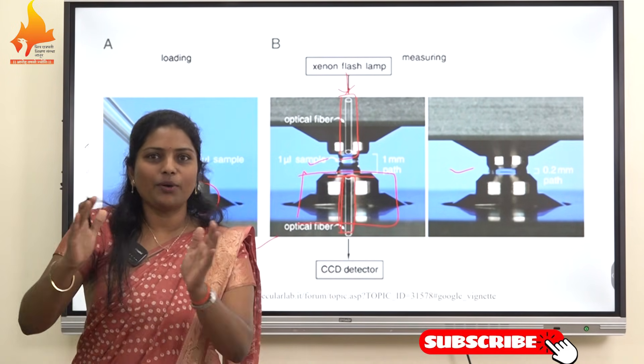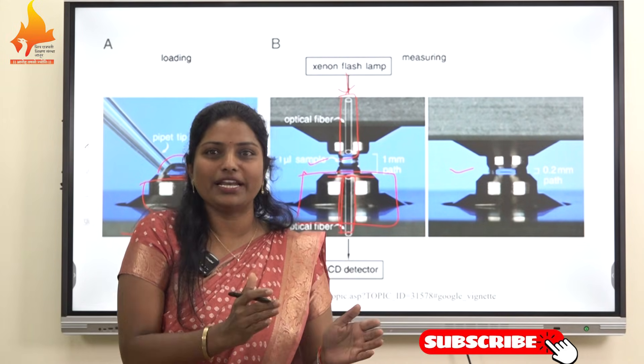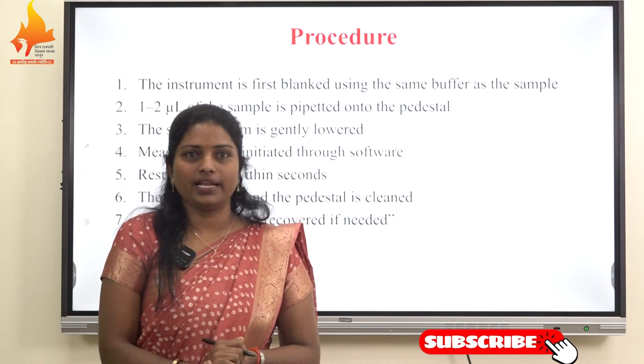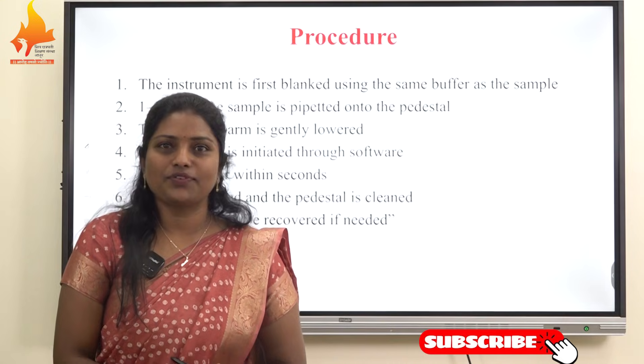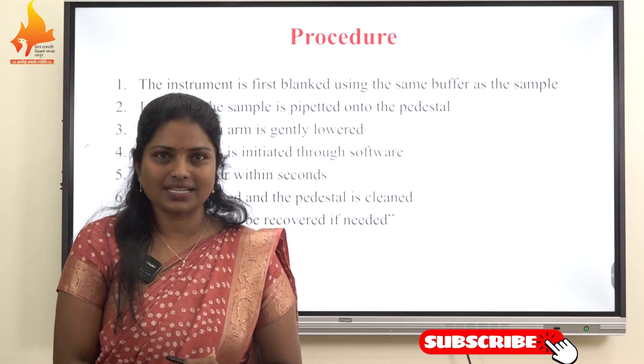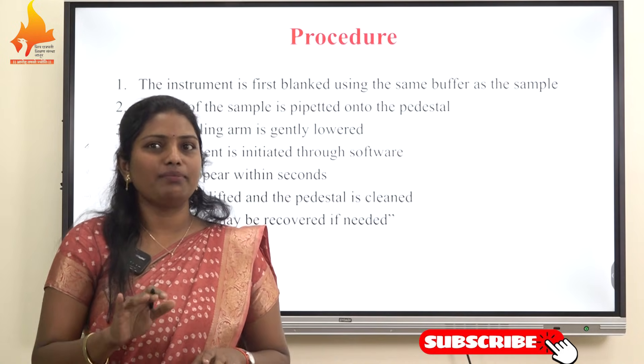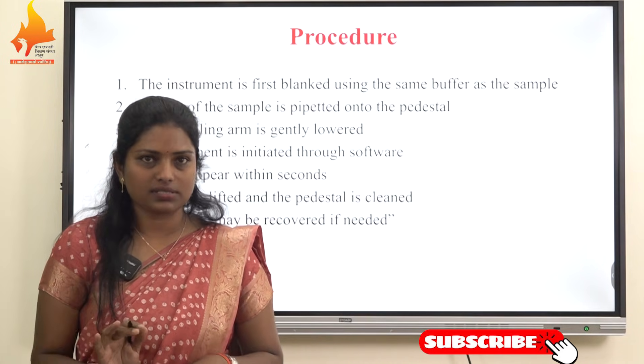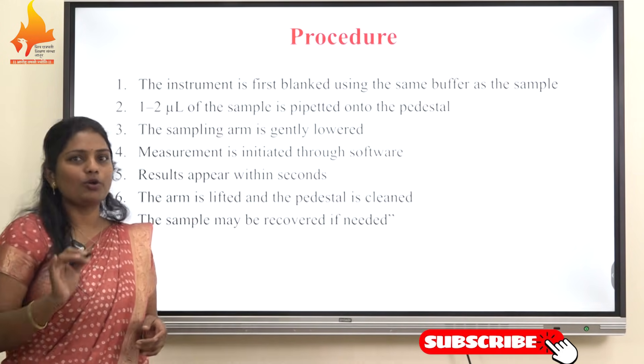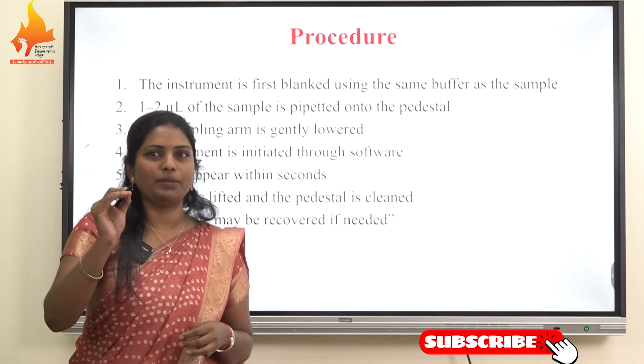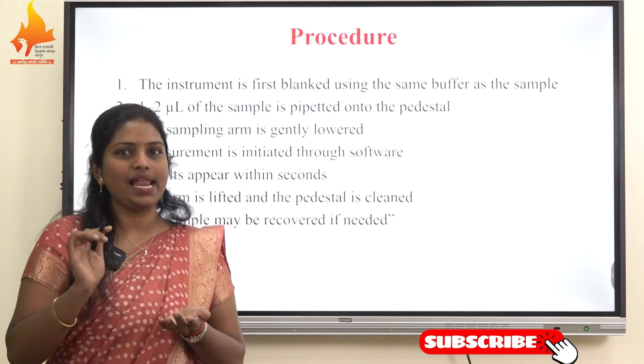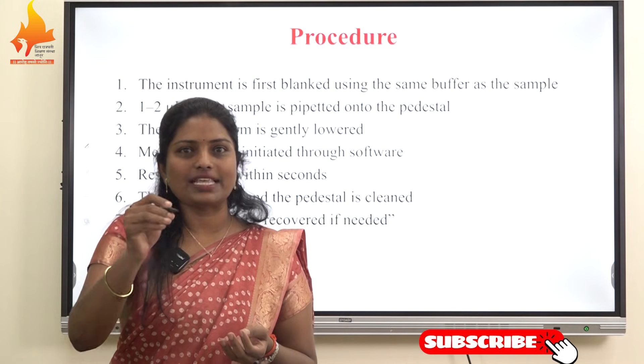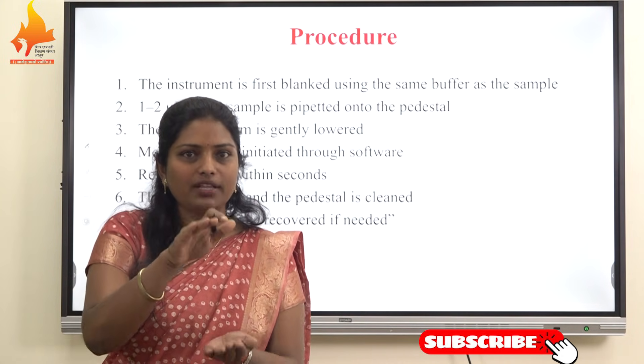The software instantly computes the concentration and purity ratio based on the preset extinction coefficients. The nanodrop analysis follows a simple and quick procedure. First, the instrument is blanked using the sample buffer or solvent present in the sample to eliminate background absorbance. Next, one to two microliters of sample is carefully pipetted onto the measurement pedestal, and the arm is gently lowered, allowing the sample to form a liquid column between the optical surfaces.